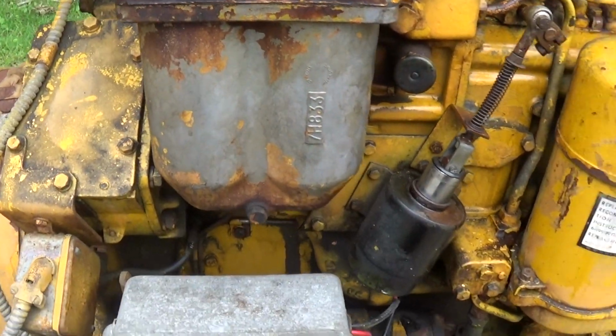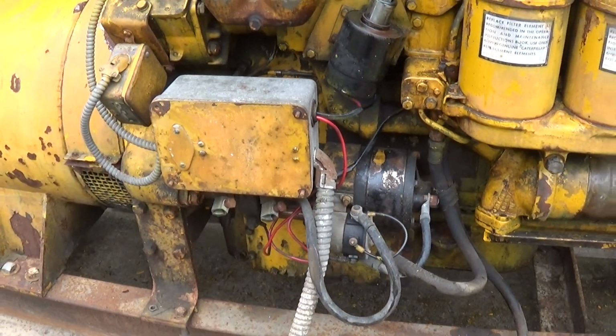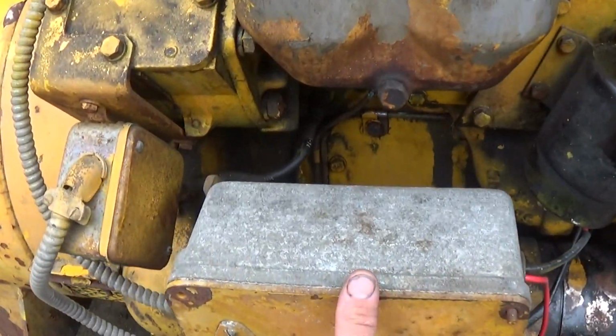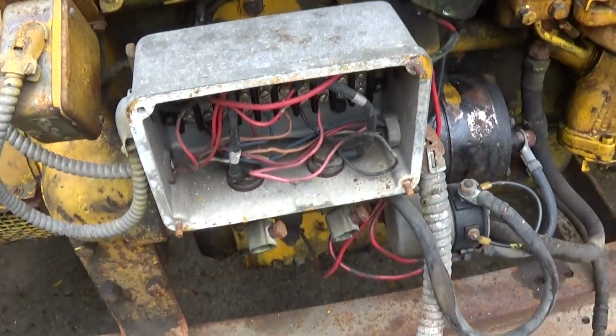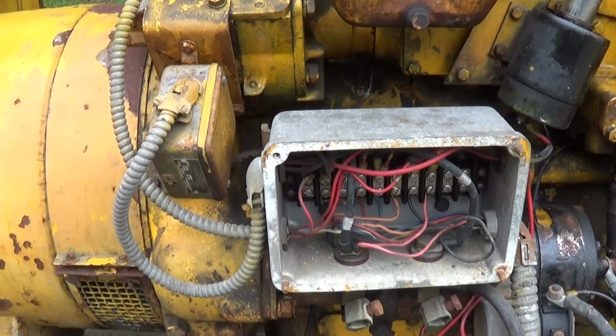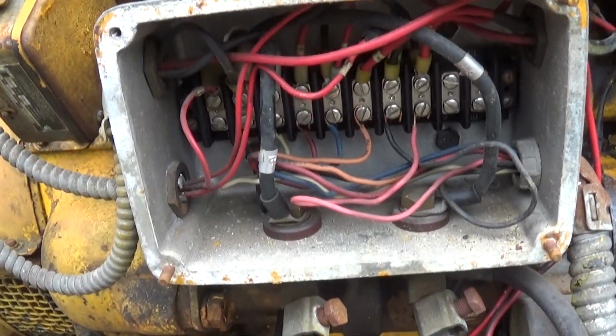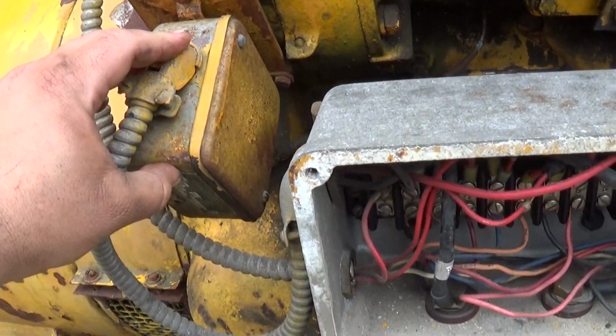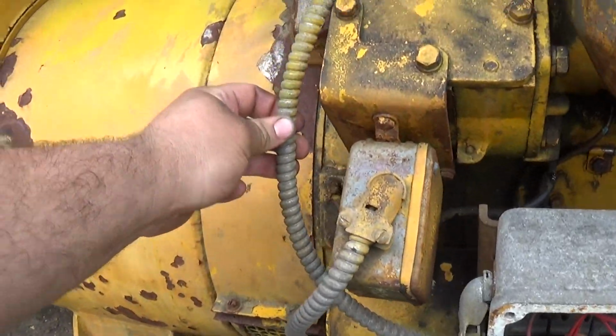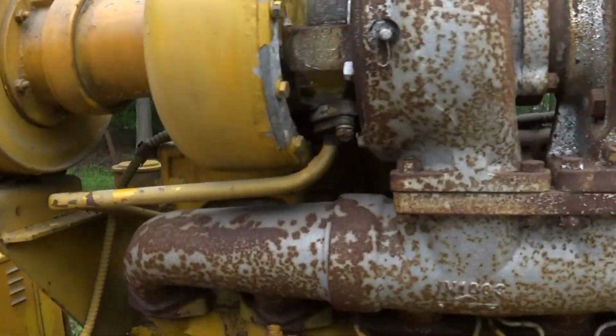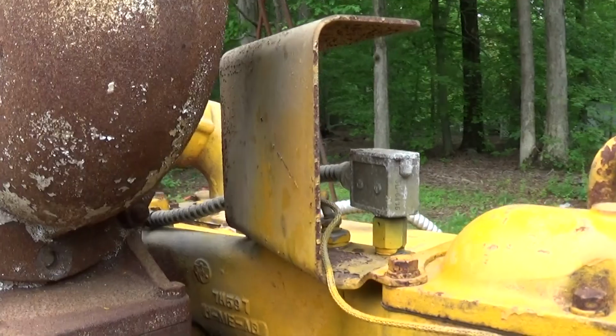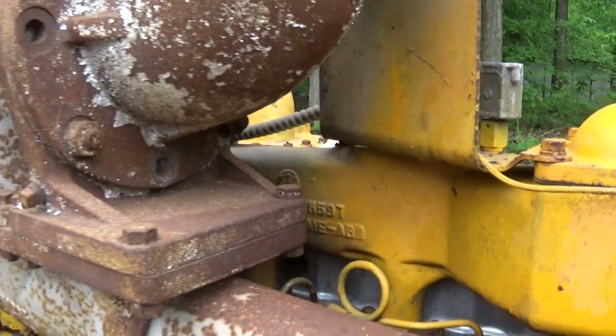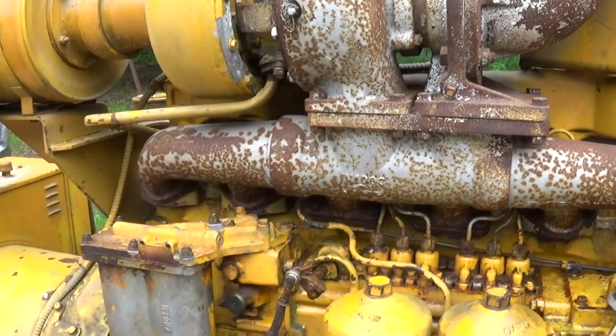Fuel filters, starter motor down at the bottom there, and this is just a connection box where the DC wiring would have terminated. Got an oil pressure switch here, and this piece of armored cable runs up to a temperature switch up here. So that would be your low oil pressure and high engine temp shutdowns.